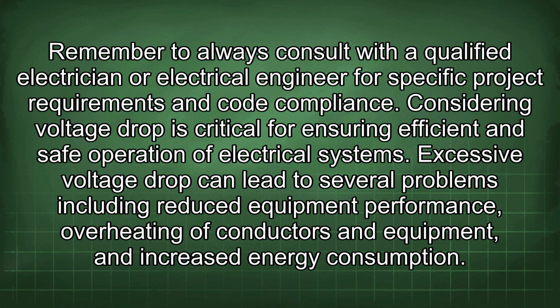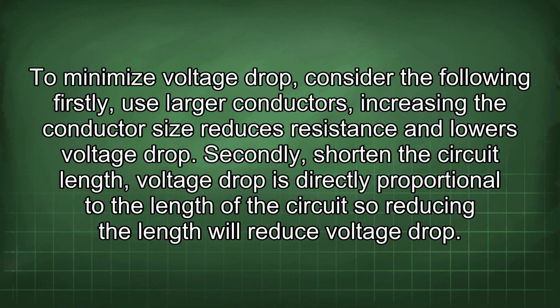Considering voltage drop is critical for ensuring efficient and safe operation of electrical systems. Excessive voltage drop can lead to several problems, including reduced equipment performance, overheating of conductors and equipment, and increased energy consumption. To minimize voltage drop, consider the following. Firstly, use larger conductors. Increasing the conductor size reduces resistance and lowers voltage drop. Secondly, shorten the circuit length. Voltage drop is directly proportional to the length of the circuit, so reducing the length will reduce voltage drop.